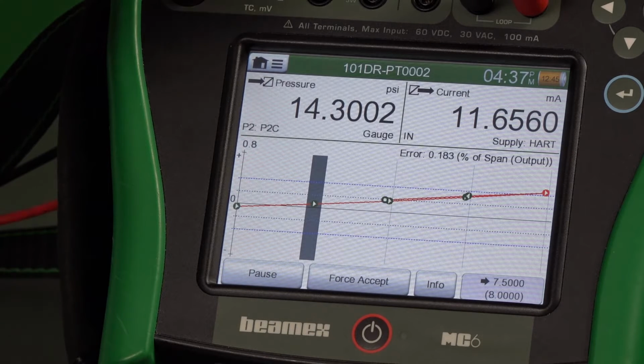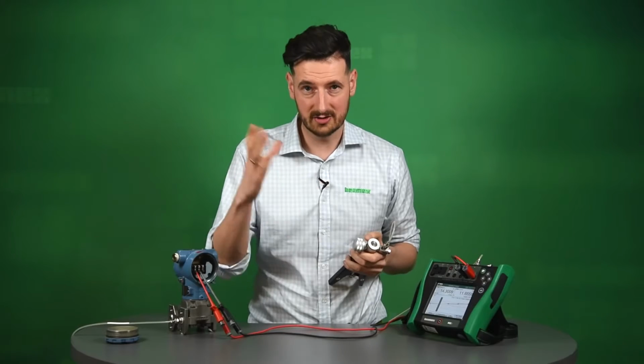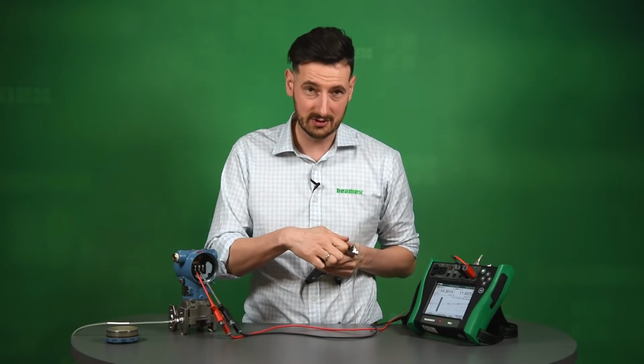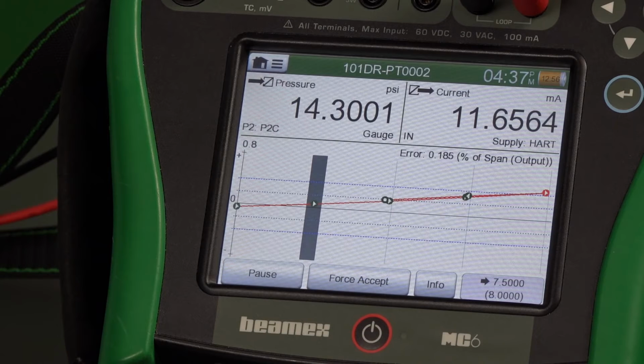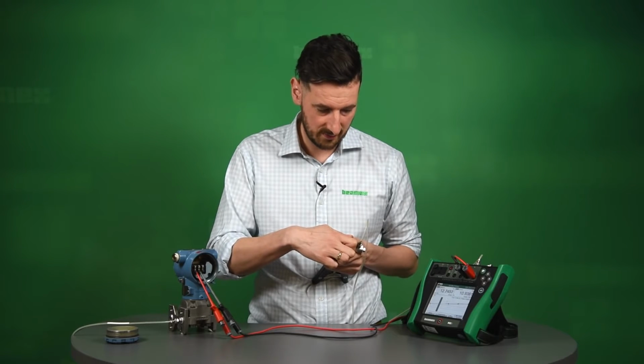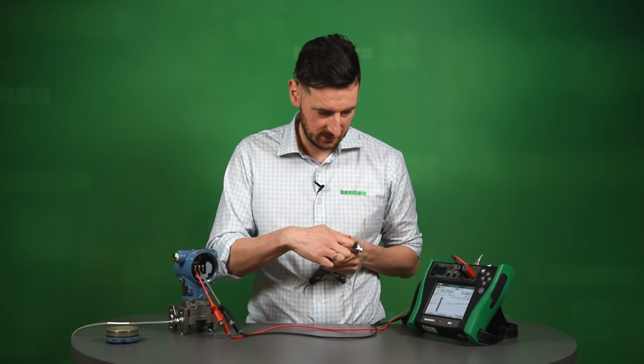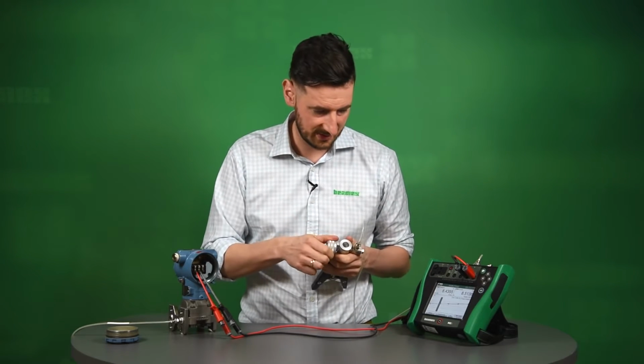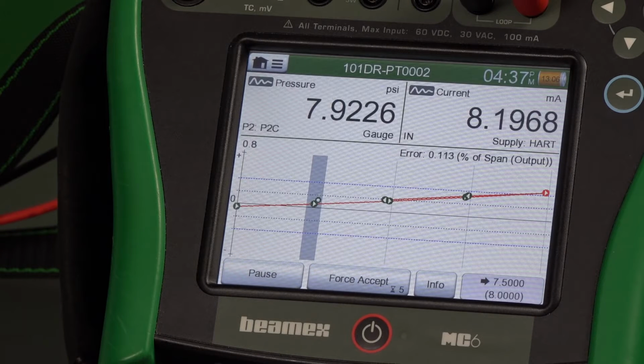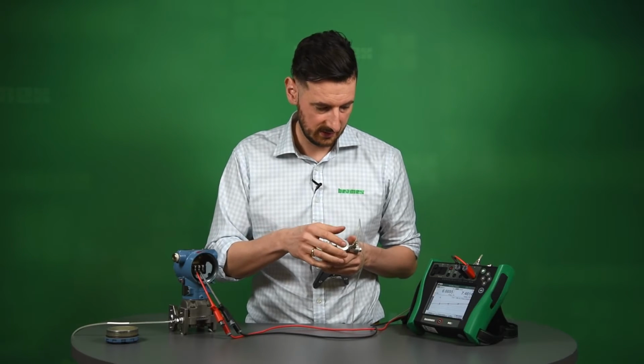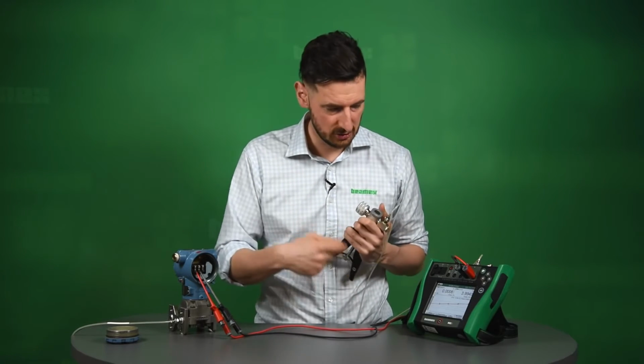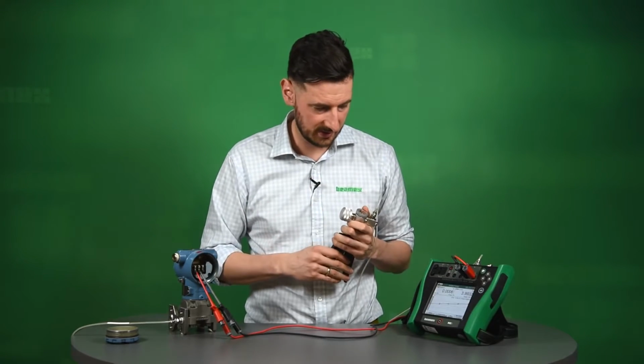You can see right now that coming down and going up, it's more or less the same line. So there is no hysteresis, which is good. That's a good characteristic of a transmitter, and we want to see that. But also, if you look at this graph, you would see that at 0, we had practically no error. The error looks as if it is on the span, so we'd have to adjust that to fix that and make sure we've got a pass result at the end. So it's fine. Let's capture the 7.5, and let's open the vent and go all the way to 0 to capture the last point. So we've done a 10-point calibration right now, 5 up and down.